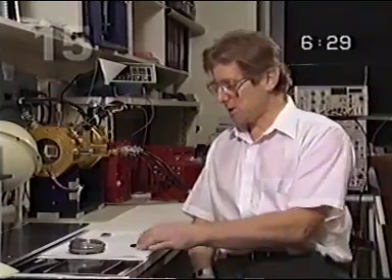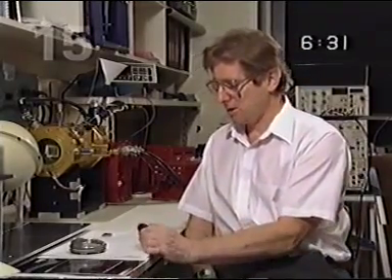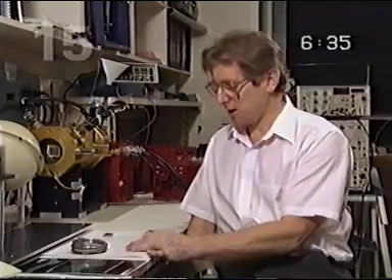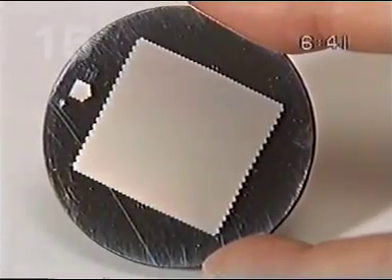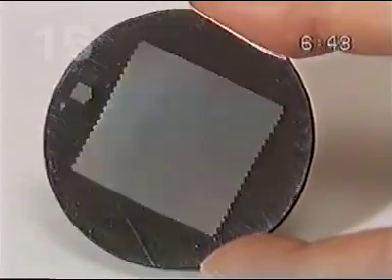For this, we need detectors which are specific to the ultraviolet, which are not sensitive to the visible and are only sensitive in the ultraviolet. Such a detector you can see here. This is a microchannel plate, and we coat this with a cathode which is only ultraviolet sensitive. This particular detector has 1,000 elements in one direction and 1,000 elements in the other direction, so you get 1,000,000 picture elements overall.